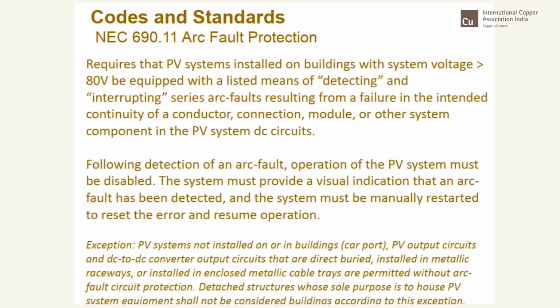And then let us quickly go through the codes and standards. 690.11 is for arc fault detection. The National Electrical Code requires that PV systems installed on buildings with a system voltage greater than 80 volts be equipped with a listed means of detecting and interrupting series arc faults resulting from a failure in continuity of the conductor. Following the detection of an arc fault, operation of the PV system must be disabled. The system must provide a visual indication that an arc fault has been detected, and the system must be manually restarted.